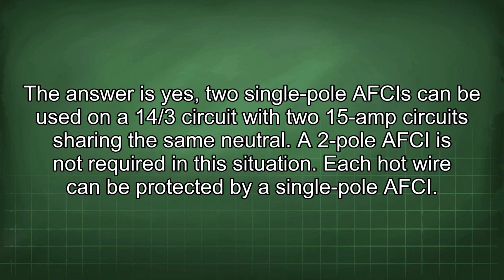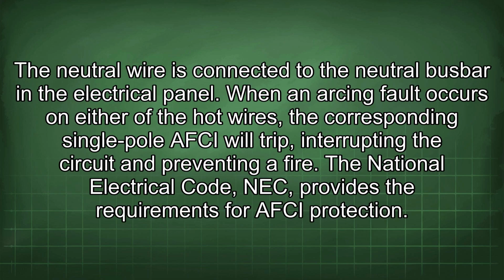The answer is yes, two single-pole AFCIs can be used on a 14/3 circuit with two 15-amp circuits sharing the same neutral. A two-pole AFCI is not required in this situation. Each hot wire can be protected by a single-pole AFCI. The neutral wire is connected to the neutral busbar in the electrical panel.